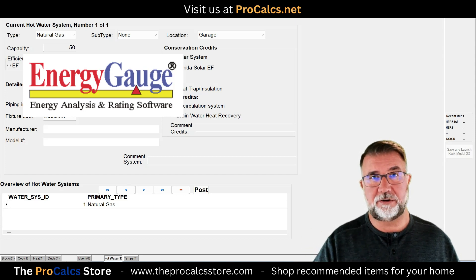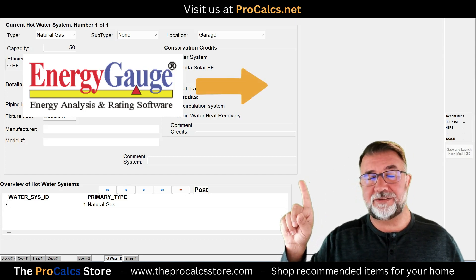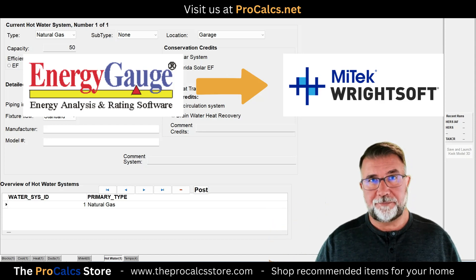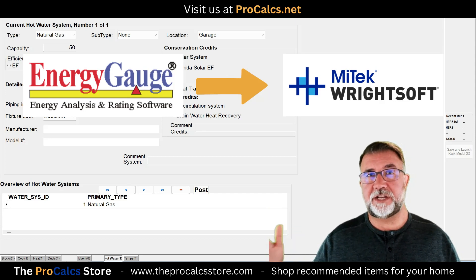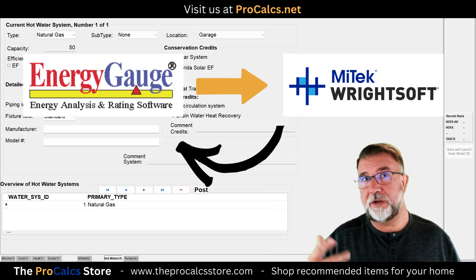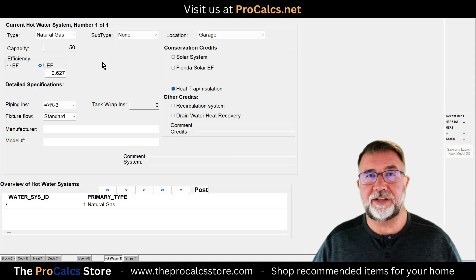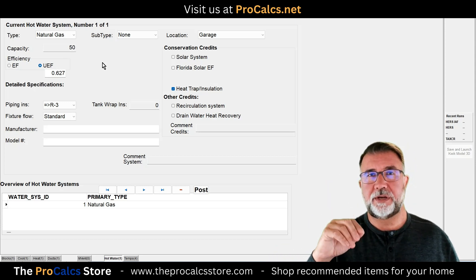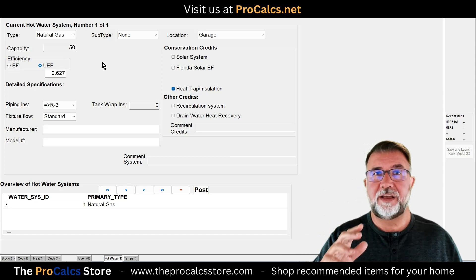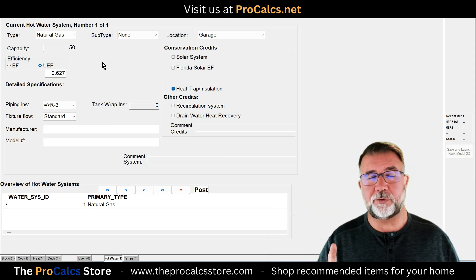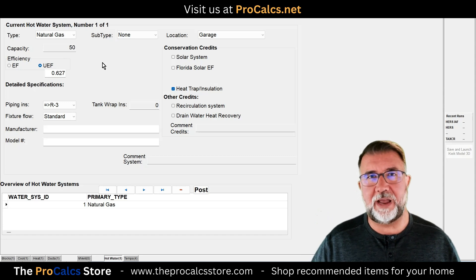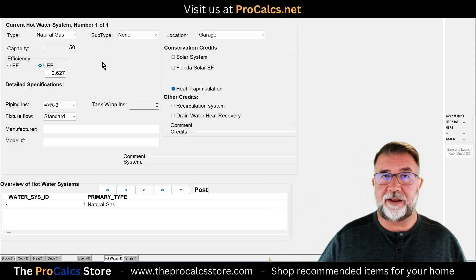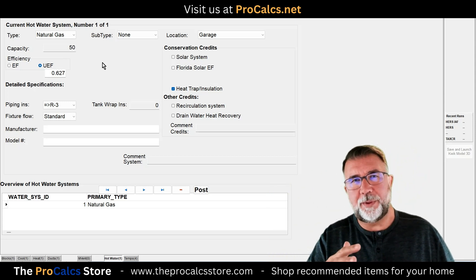The problem is if the communication between WrightSoft and Energy Gauge worked much better, we'd use Energy Gauge more frequently. WrightSoft has made it easy to convert energy calculations, but if it fails in Energy Gauge you have to make a manual change there AND go back and make that change in the load calculations as well — double work. For example, if a 14-SEER heat pump fails and you change it to a 16-SEER, you have to update the WrightSoft file too. Similarly, changing windows to more efficient ones will affect the air conditioning system size.